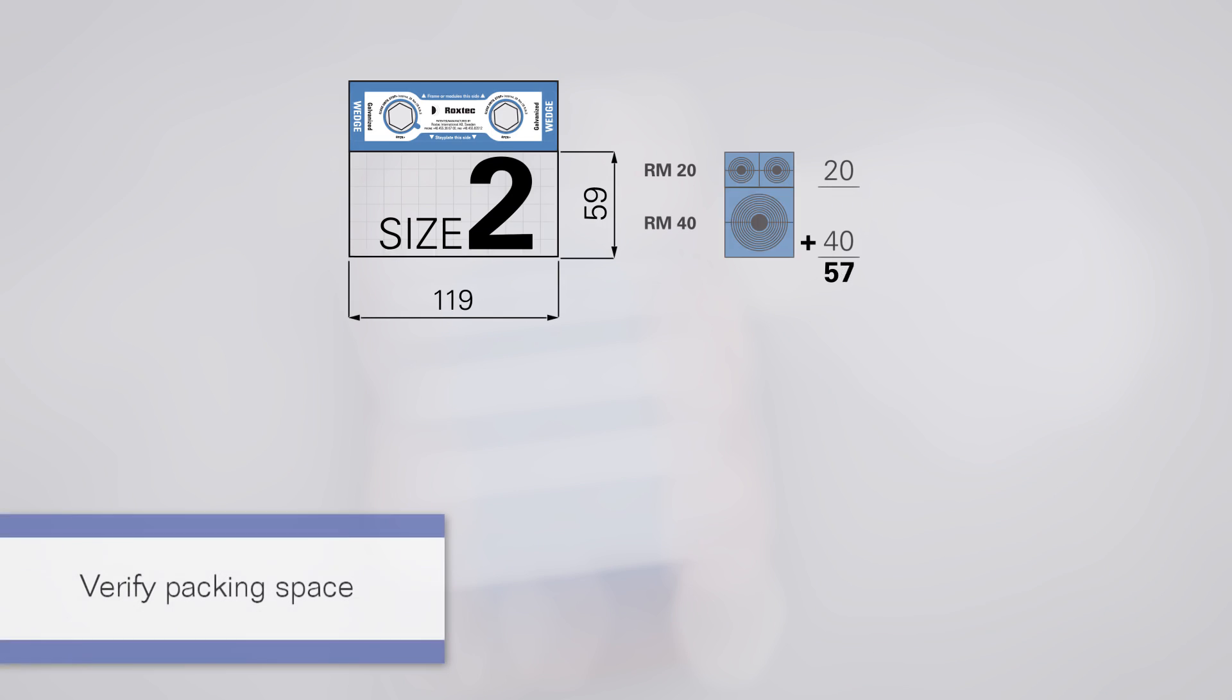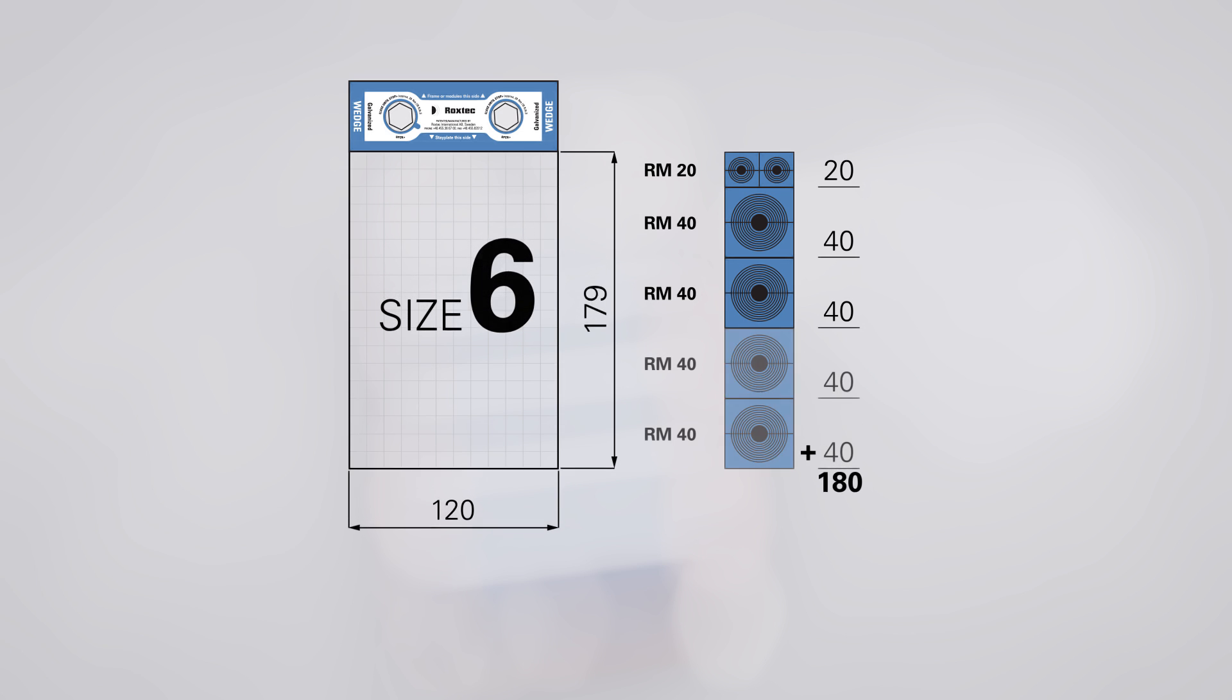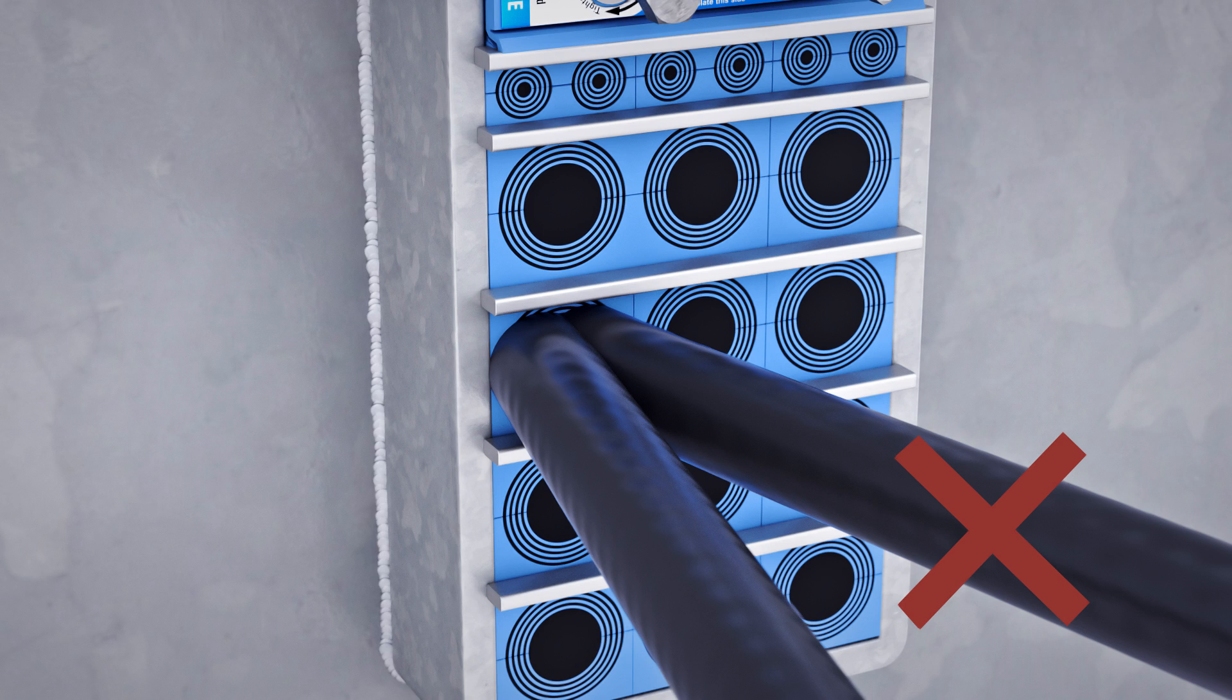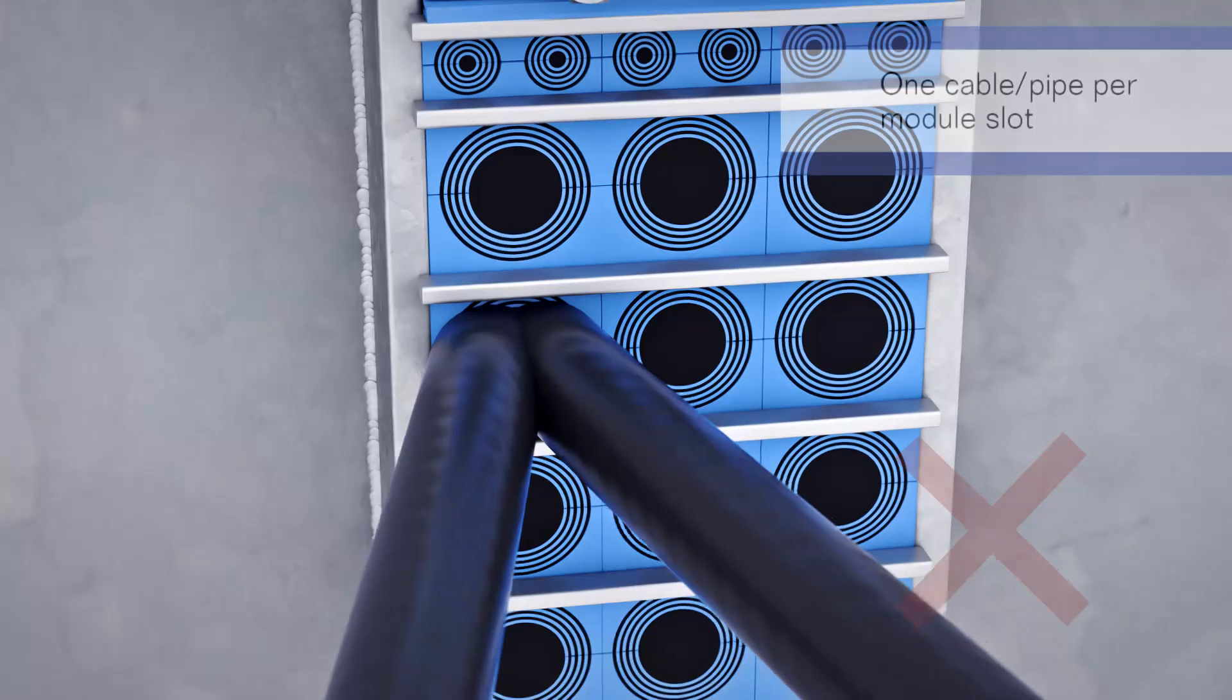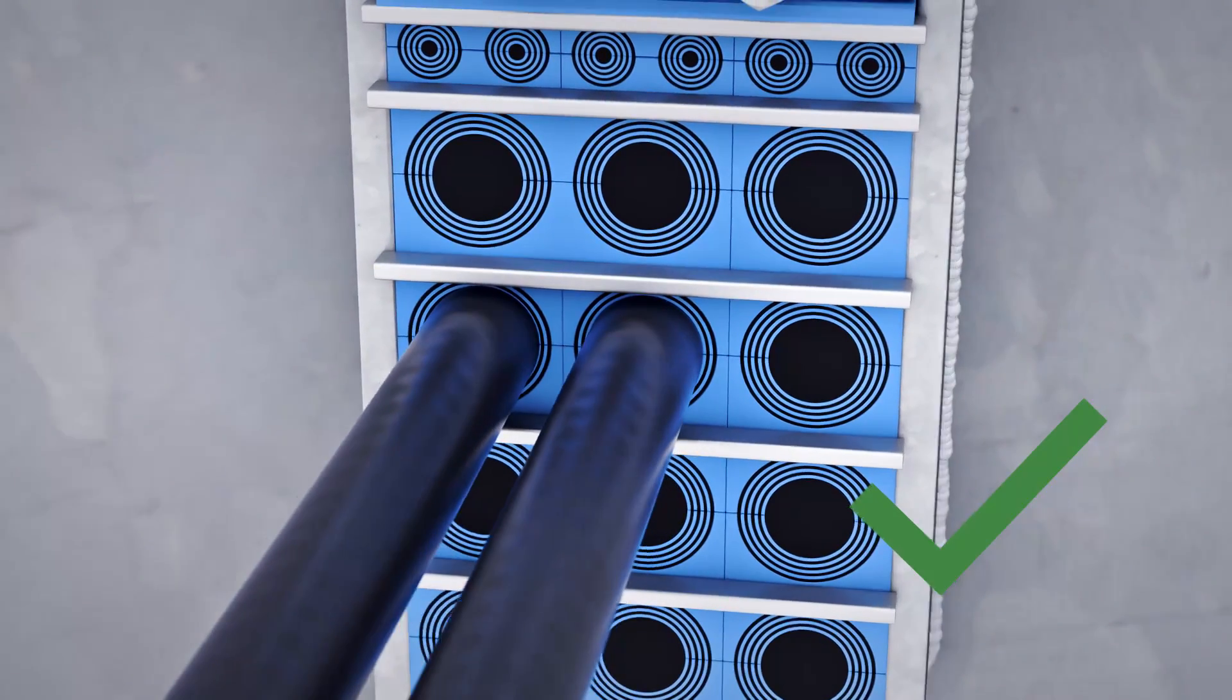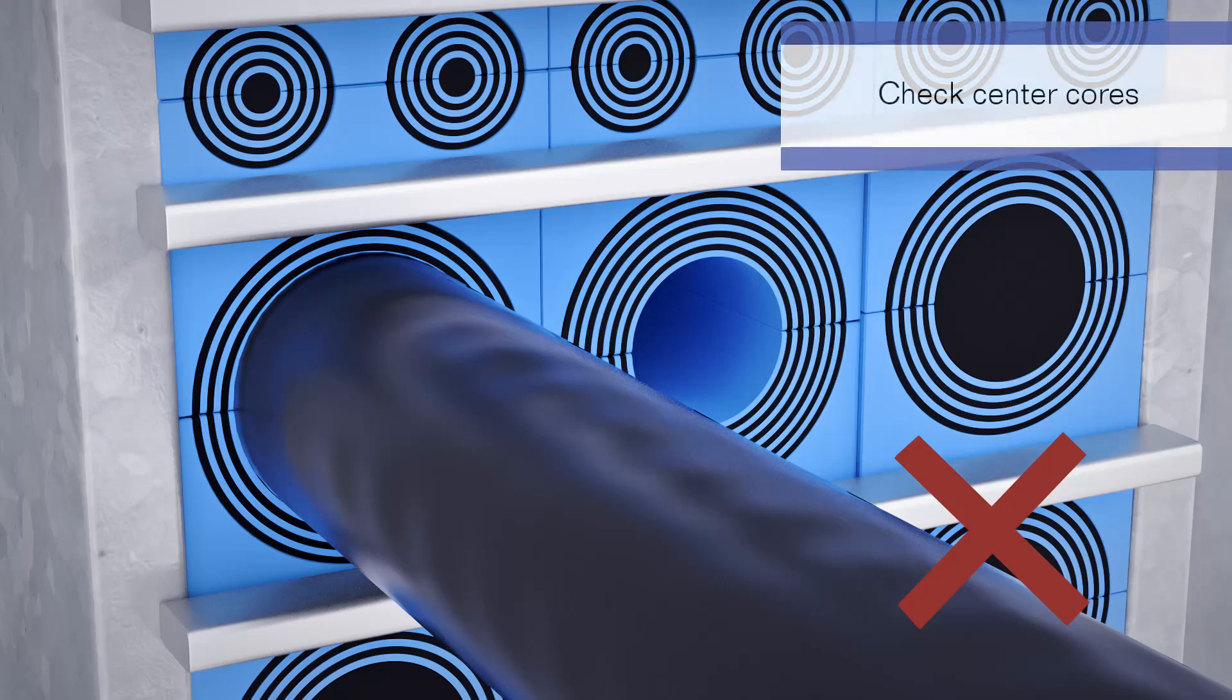Verify the utilization of the packing space according to installation instructions. Make sure that multiple cables or pipes don't pass through the same module slot. Check that there are no center cores missing.